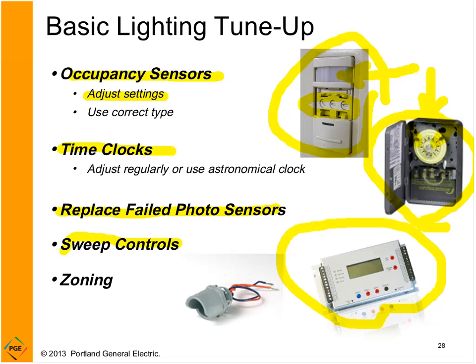Sweep controls are typically found in larger buildings. So if you have sweep controls, the key there is to have multiple sweeps. And why don't I step back and describe what sweep controls do. Typically, let's talk about an office environment. Typically, the occupants are going home around 5, maybe a few people stay till 6, but maybe in your building, people aren't there much after 7. So your sweep controls can automatically sweep off the lights, or turn off all the lights other than your emergency egress lighting. And it'll sweep those non-essential lights off at 7 o'clock or whenever you feel it's appropriate. That's a great way to control your lighting energy consumption.